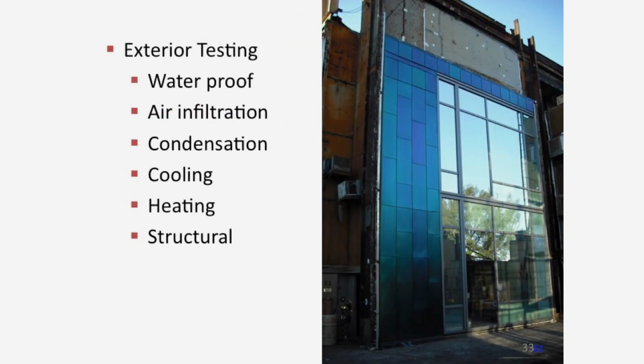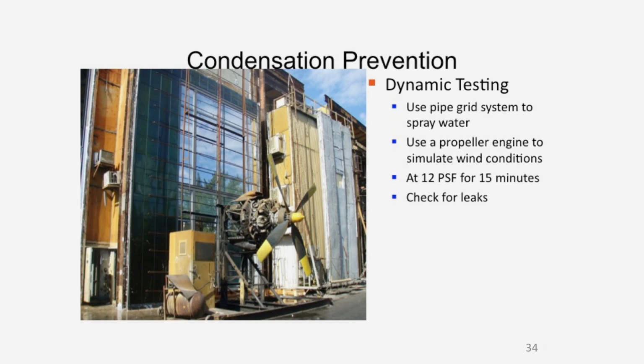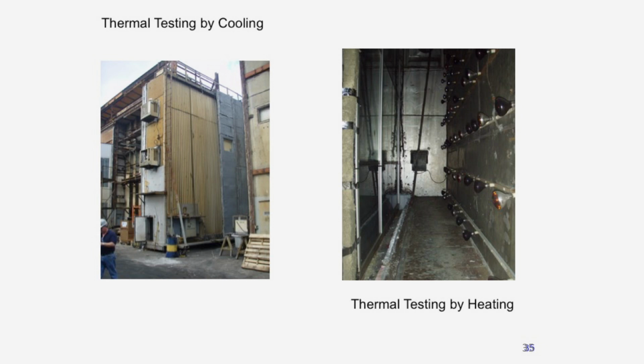When we built our latest hospital, one of the very first things we asked for, for mold management reasons and, unbeknownst to me at the time, energy reasons, was a good exterior wall. So we built a mock-up to make sure we got what I wanted, which was a waterproof wall. It was mocked up down in Florida, and they put an airplane propeller in front of it and a series of pipe grids that sprayed water onto the surface of that mock-up when the propeller was turned on, to see how much it leaked. In addition to that, we heated it and cooled it to see what the expansion-contraction factors were when this exterior surface was exposed to that, again to give us that really, really tight exterior. Why is that important?